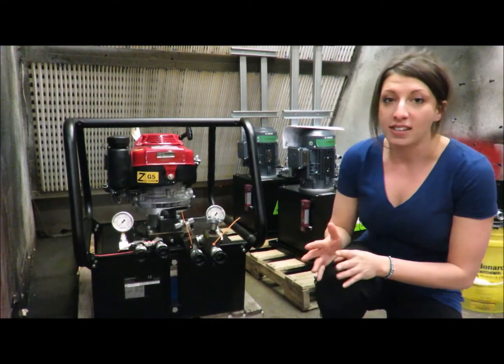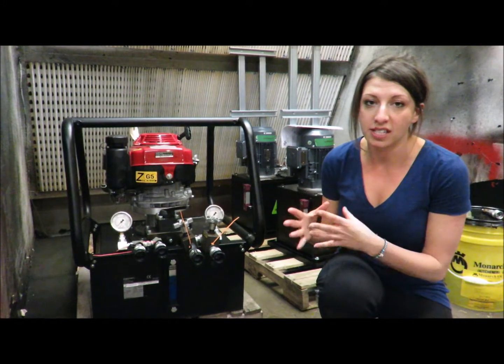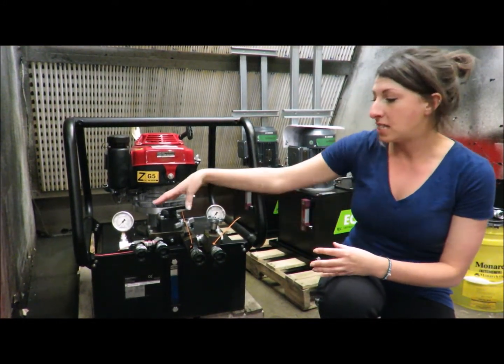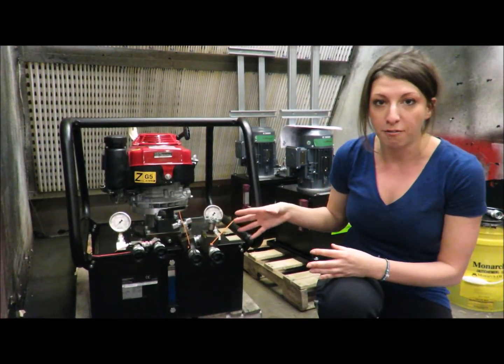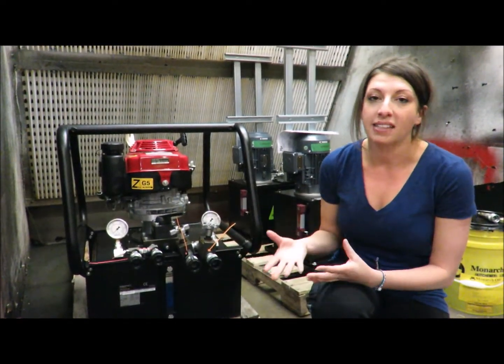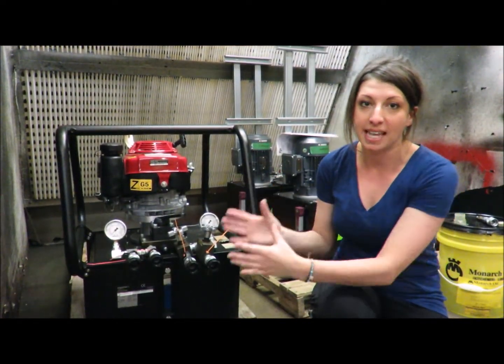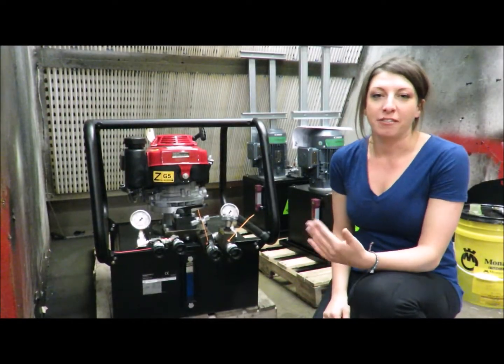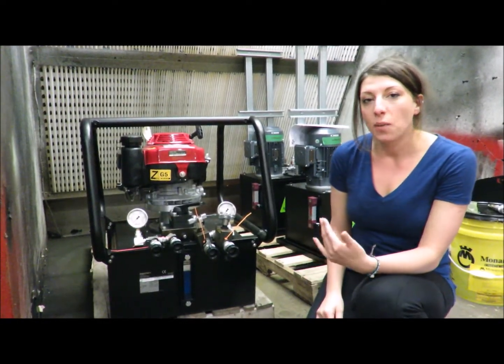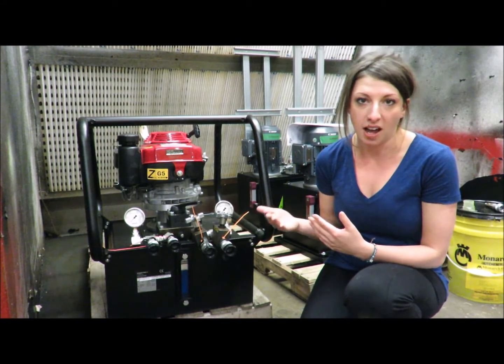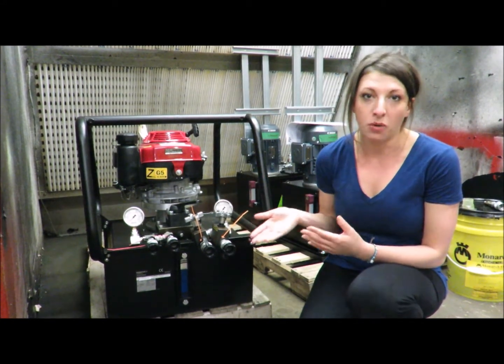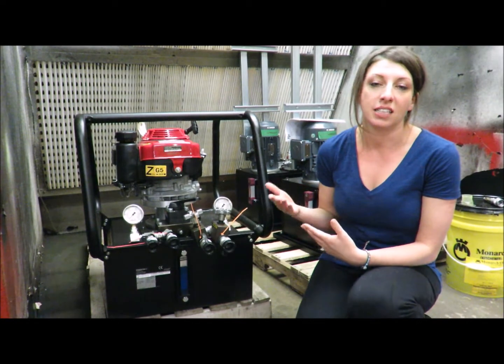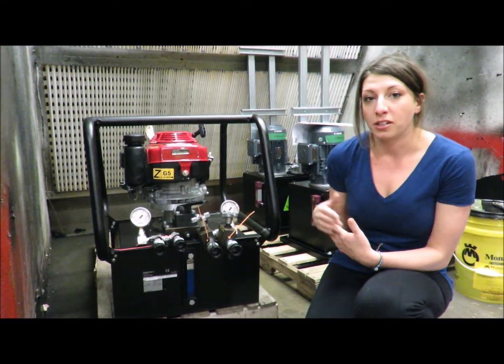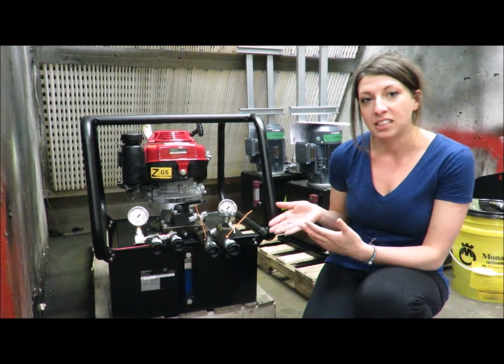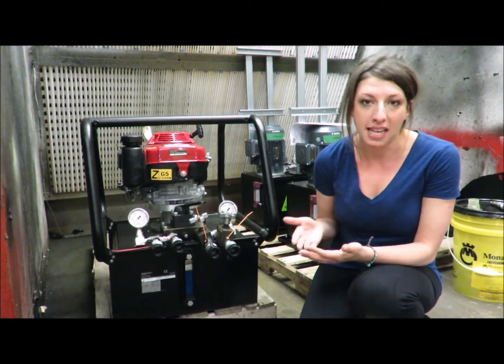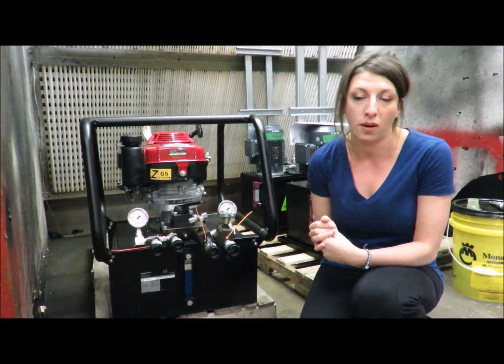In a conventional or non-synchronous power unit like this one here, there's a single oil supply. So even if it's split into separate outlet lines using a manifold, everything is connected and so they act as one. So the pressure is going to remain the same on every line. Using an example of jacking a transformer on 4 points, if the load is even slightly heavier on one side, the cylinder with the least load is going to extend more quickly than the cylinder with more load. What that means is that when you're jacking, you have to jack end to end to ensure that the load doesn't become unstable and prevent any tipping or unwanted movement.